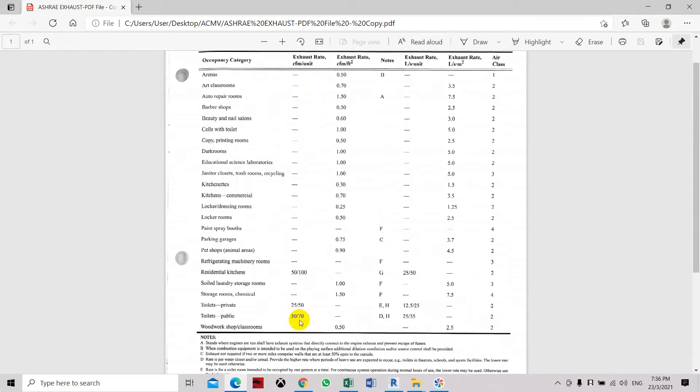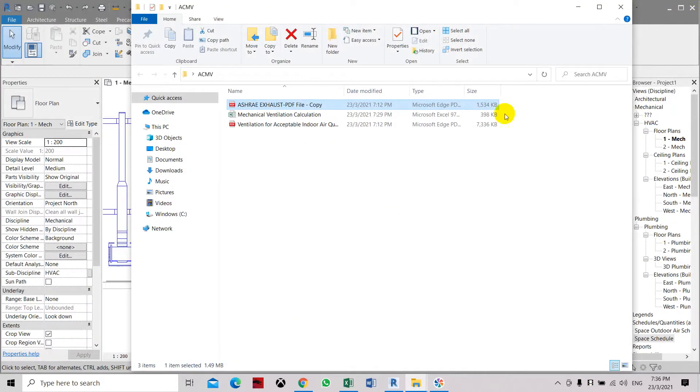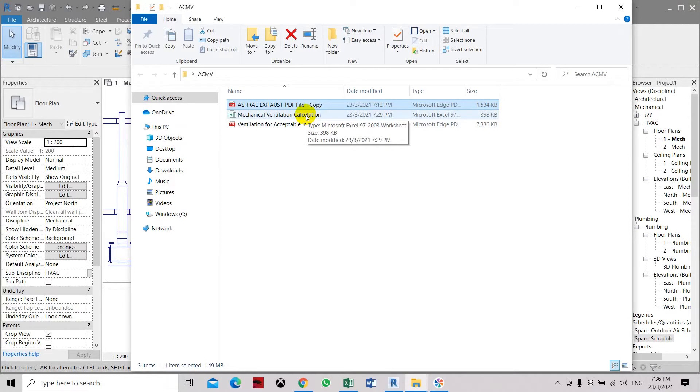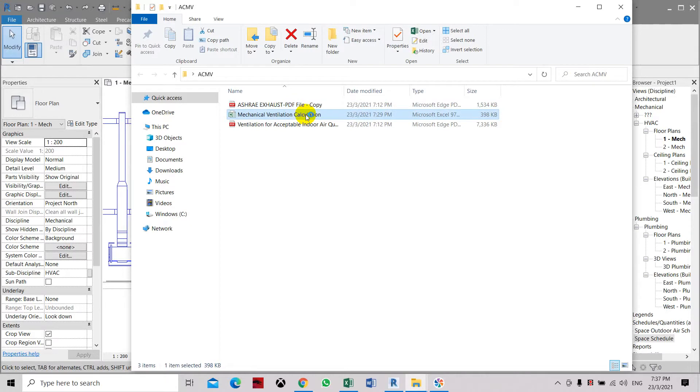You don't have to calculate by volume and air change. Another method is using the air change method. Typically the room will be ventilated on the number of air changes per hour of the room. It means the whole volume air flow of that room will have 8 air changes. It will replace the air 8 times in 1 hour.